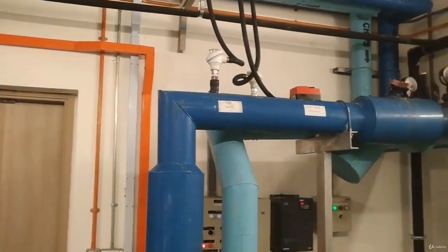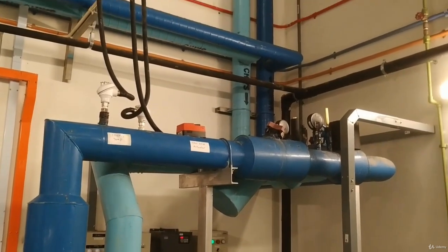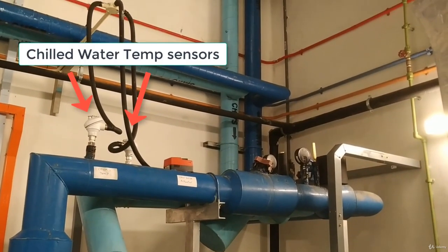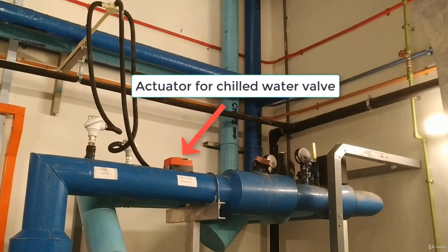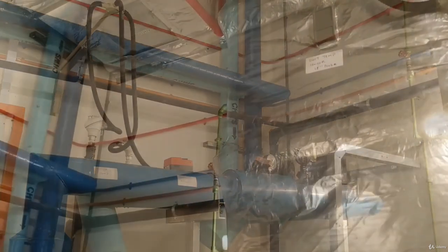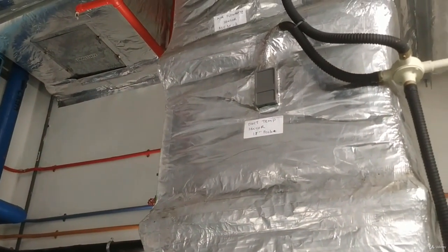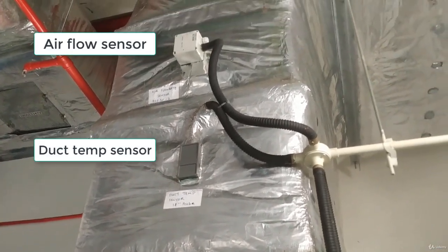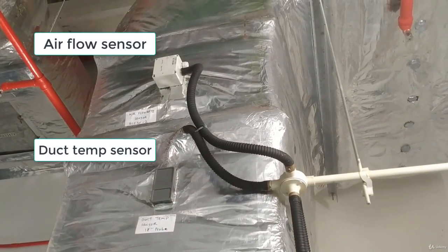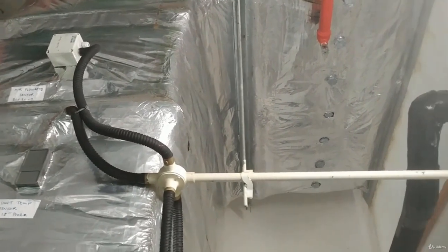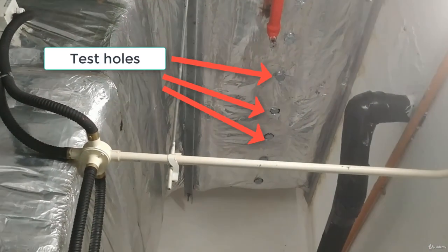Let's take a look at the different sensors or actuators you can find in this room. Over here, you can see the thermal well where the chilled water supply and return temperature sensors are. And this actuator here controls the chilled water valve that modulates the chilled water flow rate into the cooling coil. At the supply air duct, you can see the airflow sensor and the supply air temperature sensor. These are the test holes where you can insert the airflow probe into the duct to measure the airflow rate.